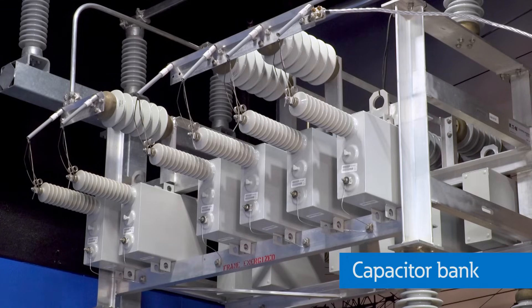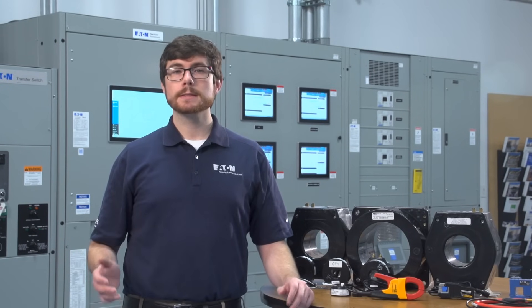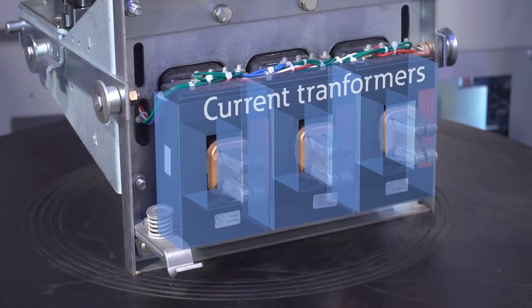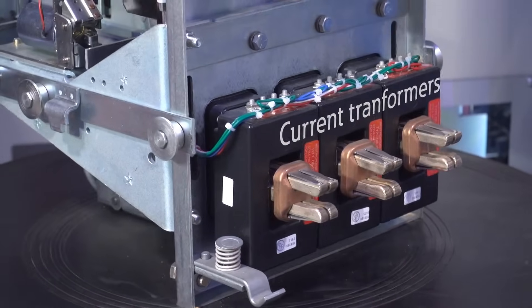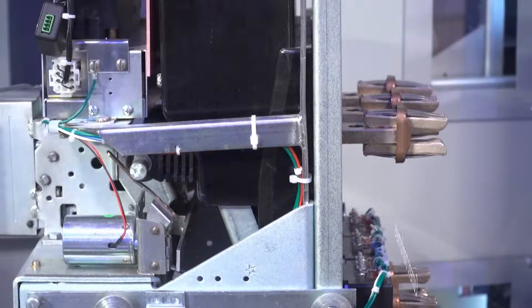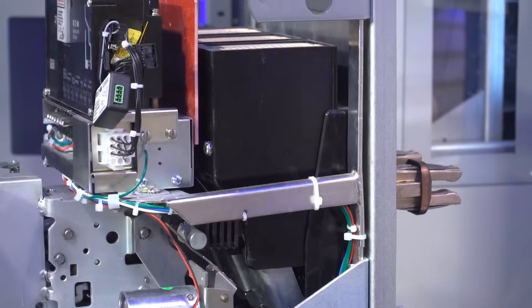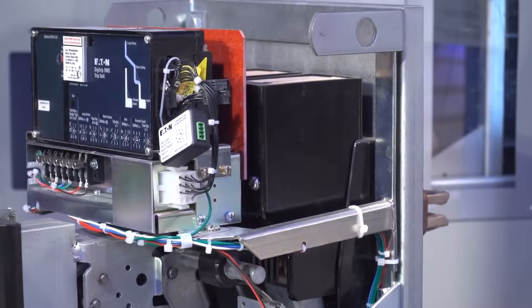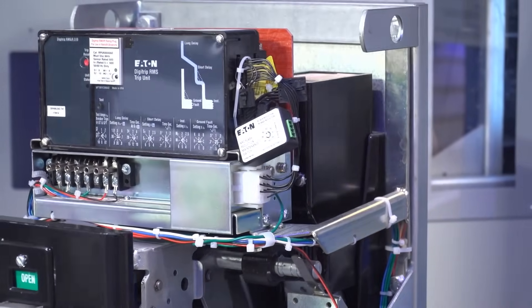Permanent CTs are also used to monitor power and power factor so that real and reactive power can be optimized. On the protection side, CTs can be used in combination with trip units for low-voltage circuit breakers and relays for medium-voltage breakers to trip the breaker when there are overloads or faults on the system.